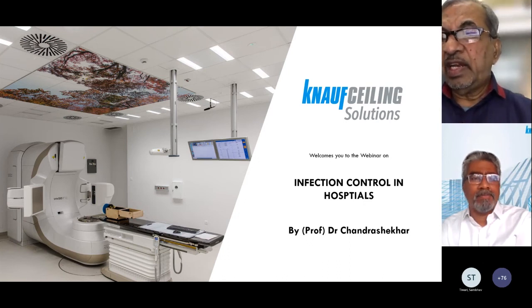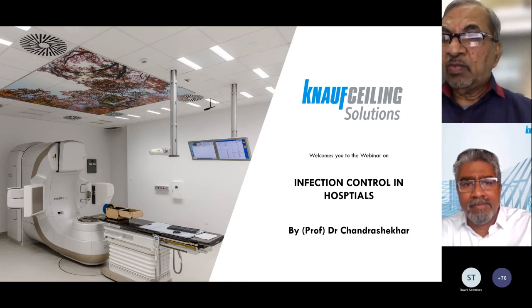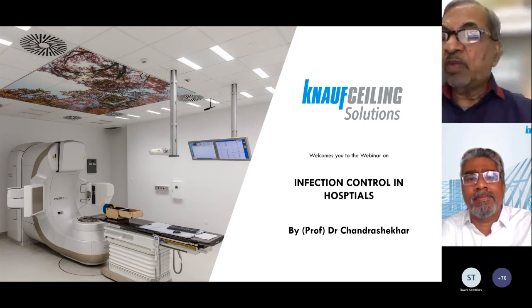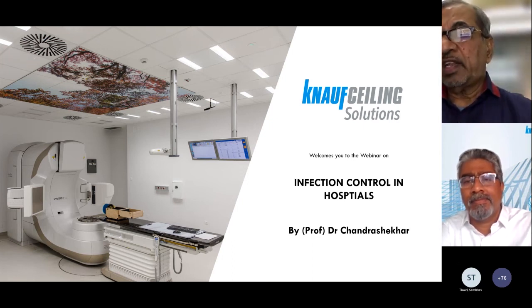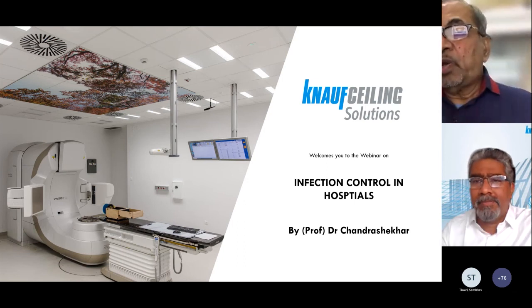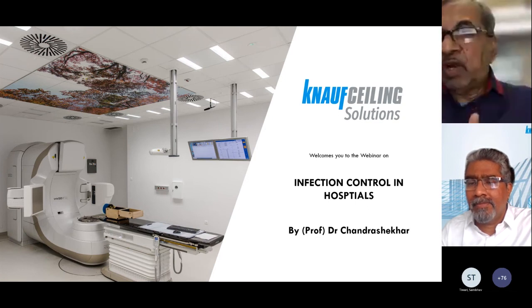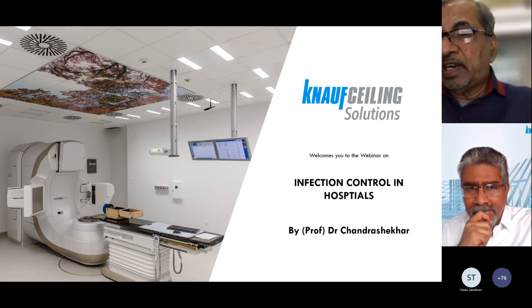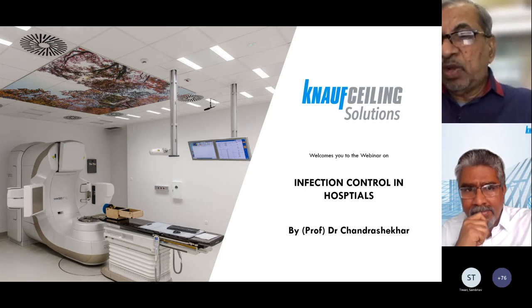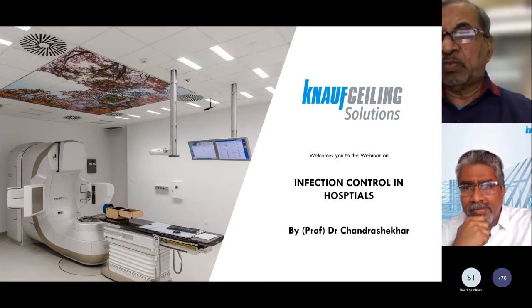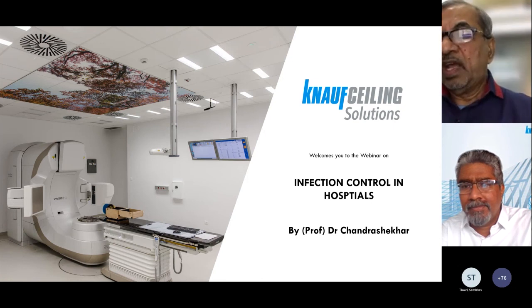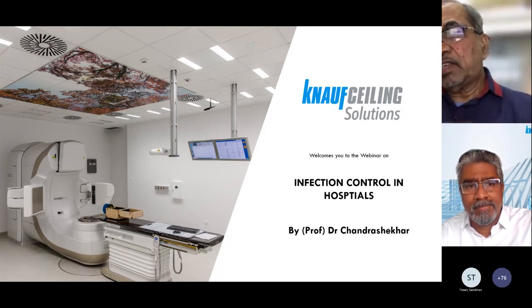What we do in pressurization is keep the corridor at positive pressure. Then in between, the lobby—where you have the toilet entry and where the fan coil unit is also kept—that lobby goes into negative pressure. Then the toilet goes into more negative pressure, and the shaft is the extreme negative. And the room is in positive pressure.